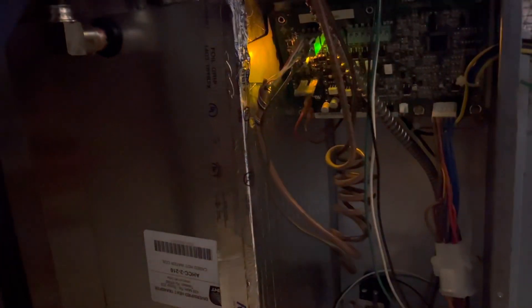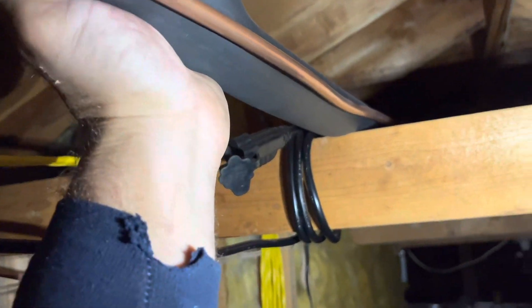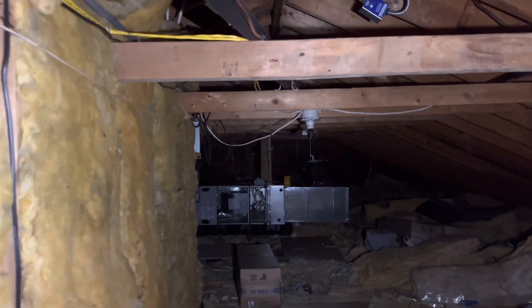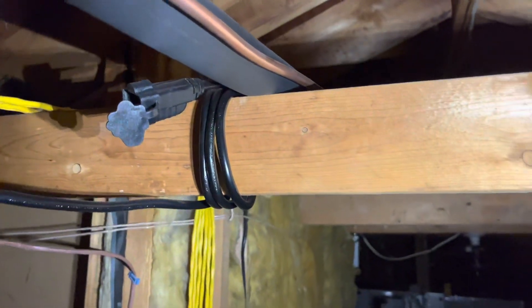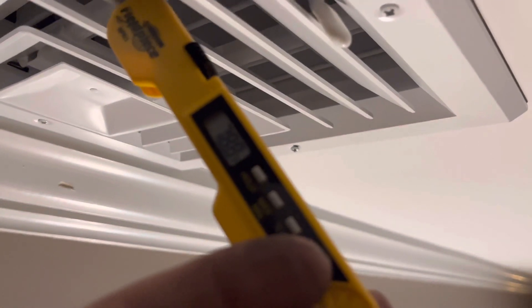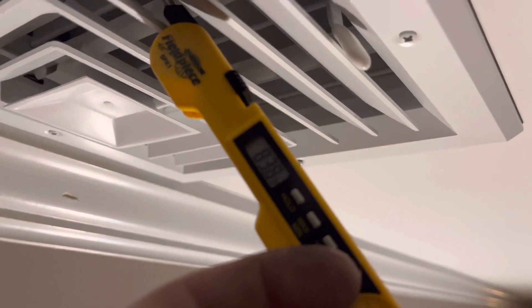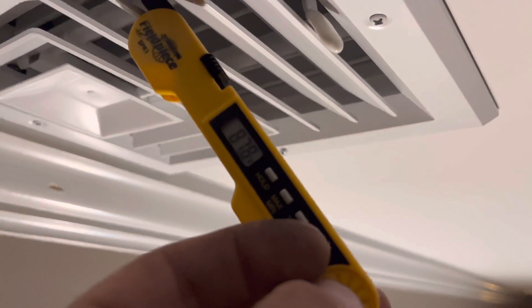It's not running. The boiler might be off too. Pump's heating up right now. We're in the middle of a second install here, so the installers must have turned the power off. But right now I have my heat pump running, so at least they have heat on one of the air handlers. We're going to go downstairs and check the heat pump outside. So it just looked like they had shut them off? Looks like somebody hit the disconnect maybe when they were pulling the auxiliary from the boiler — they were doing all kinds of things, had to run a bunch of lines up. It's just an easy mistake. But your heat pump's going right now.